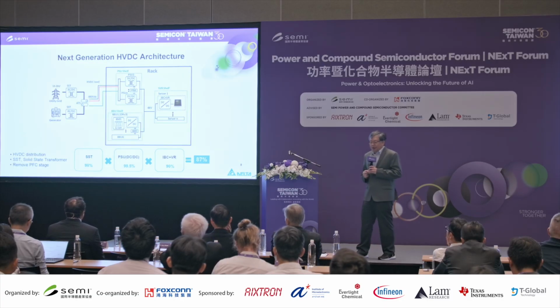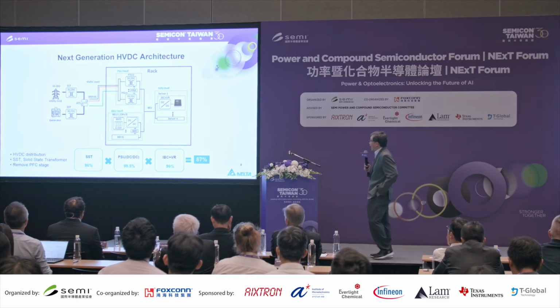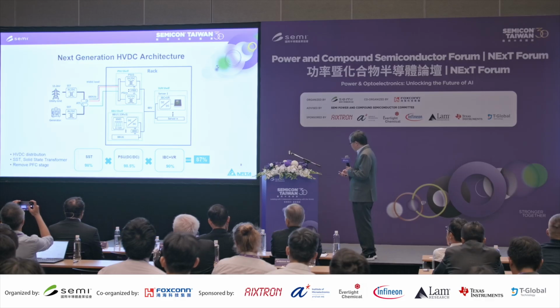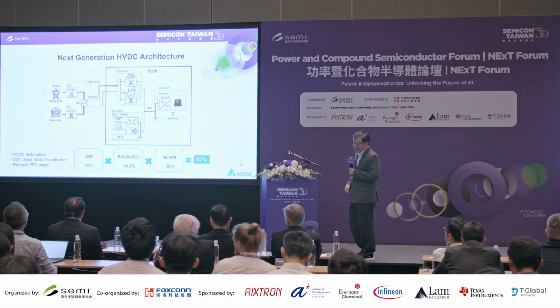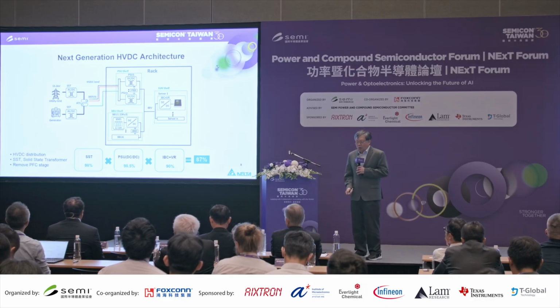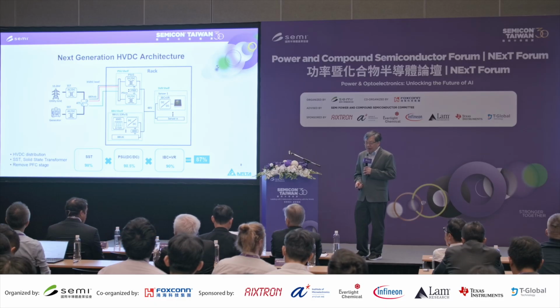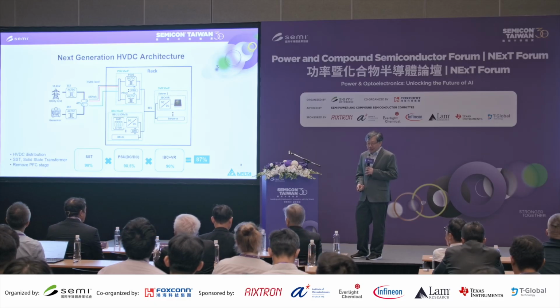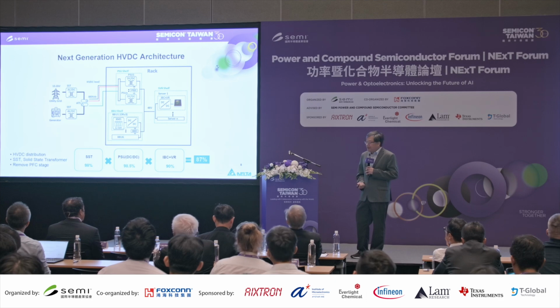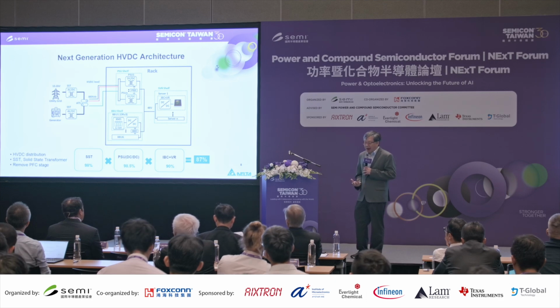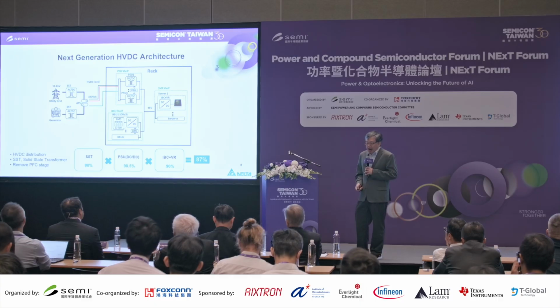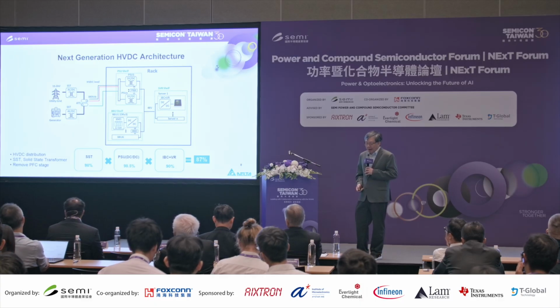This is the next generation, the high voltage DC architecture. From the power plant, we have the solid-state transformer going from AC directly to DC, for example 400 volts. This solid-state transformer probably needs silicon carbide, needing a couple thousand volts breakdown voltage, and the DC power goes all the way to the rack.